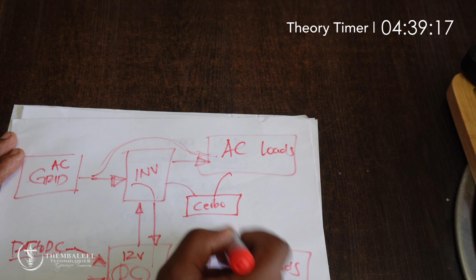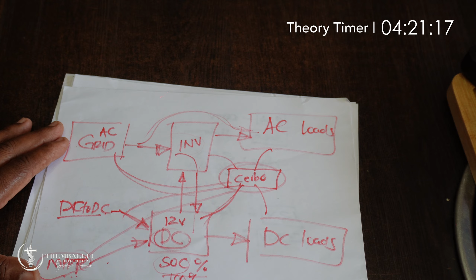For instance, let's say your state of charge is almost at 100%. Now the Cerbo needs to read that value and tell the MPPT, the DC to DC, the grid that I don't need power anymore, the battery is charged up. So lower the current that comes in, lower the power that comes in, allow the grid to bypass, create scheduled charges, save every day from such and such a time, do charge at max, go bulk charging, float charging, absorption, and so on. All this is decided by the Cerbo or any GX device.